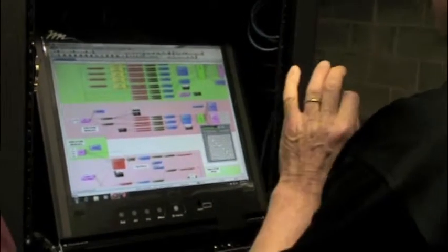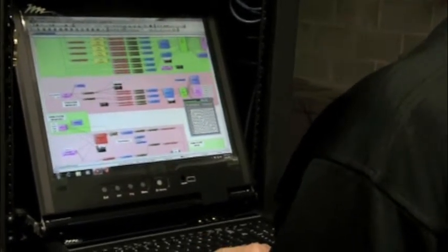When the emergency system is activated, a circuit trips upstairs, and a logic circuit trips upstairs. It basically mutes everything. This system literally mutes everything. The only thing that's going to be active is a fire control mic, which I'll show you upstairs.